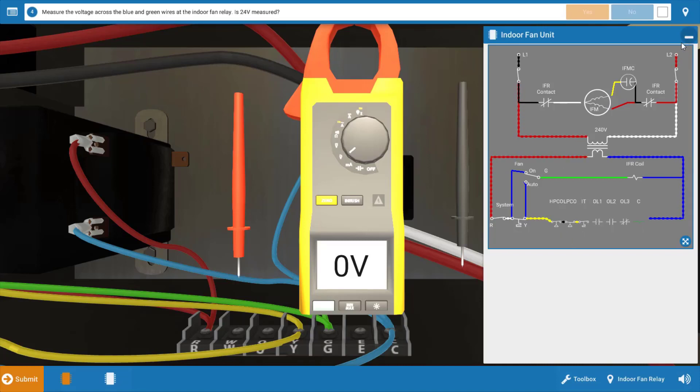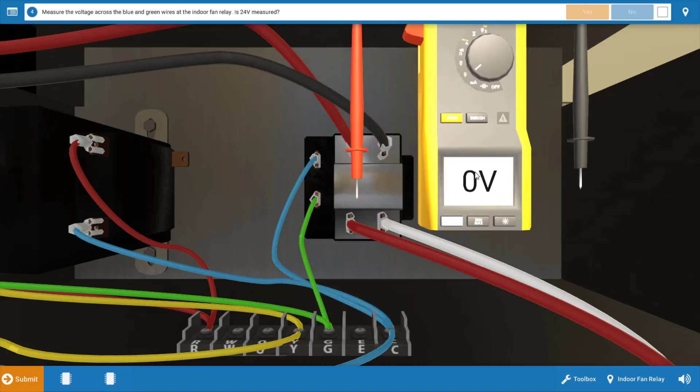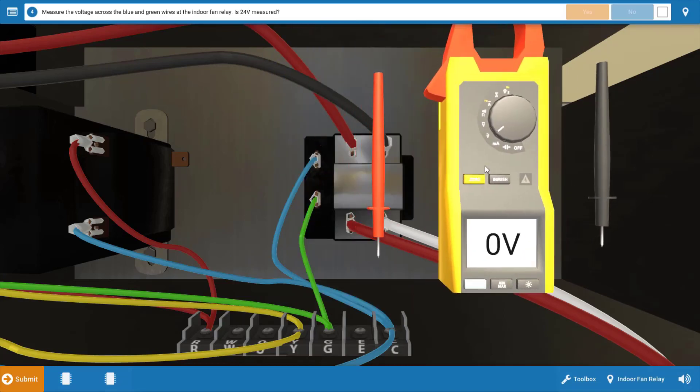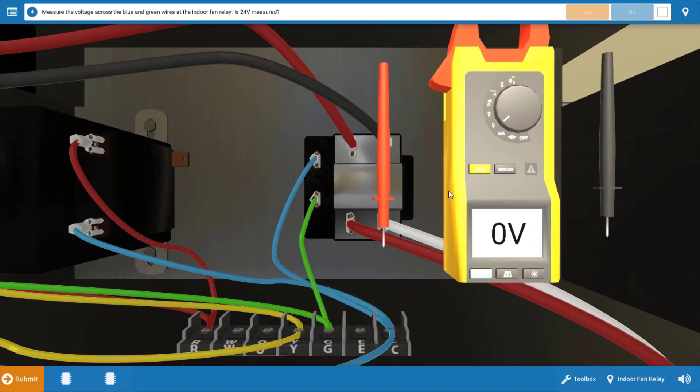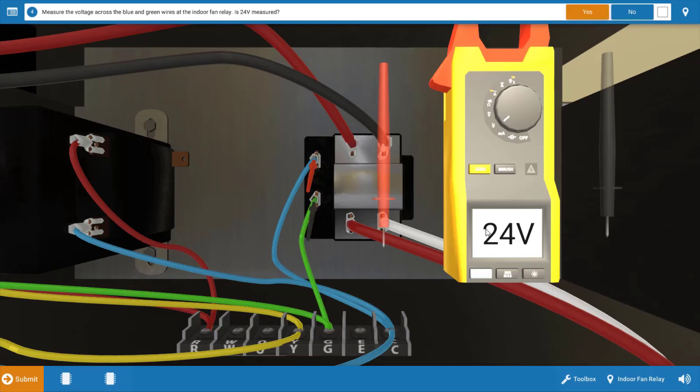So our next step is to measure at the indoor fan relay coil. Now, this is going to be the green and blue wires right here, and we should measure 24 volts here. So place your meter leads at the glowing orange hot spots, and we have 24 volts going to the relay coil.